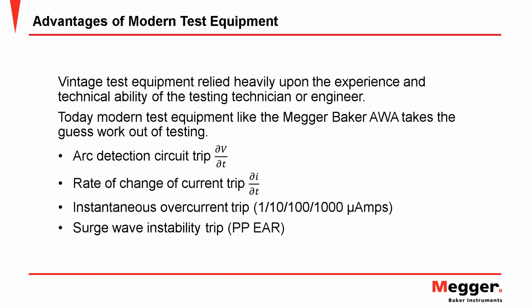And of course, when we do surge testing, we have this threshold we call pulse-to-pulse EAR, which stands for error area ratio. Basically, what that's doing is looking at the stability of that waveform. If the waveform starts to shift around, that PPAR will basically quantify that shifting and stop the test, so that we don't continue to surge while an indication of weakness has been detected.